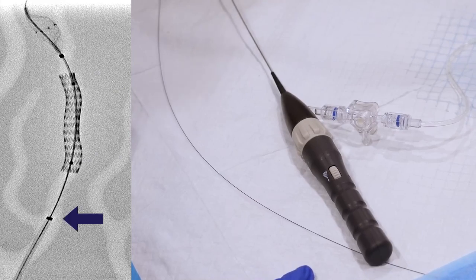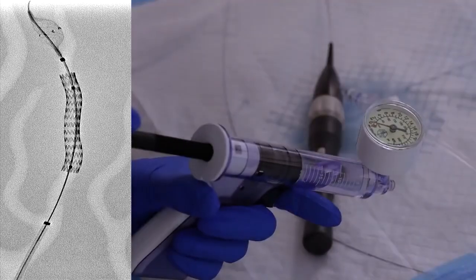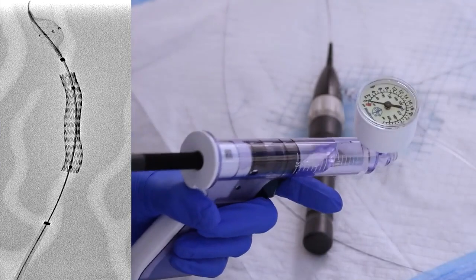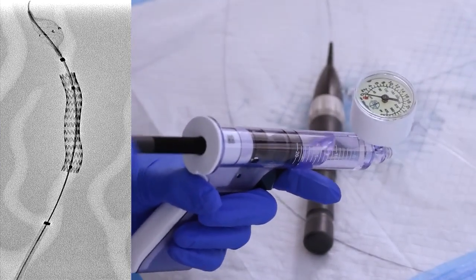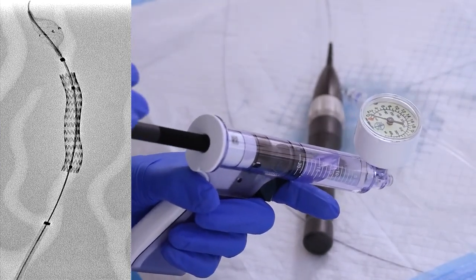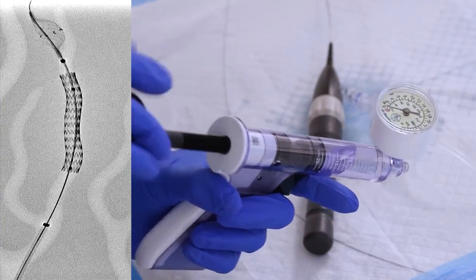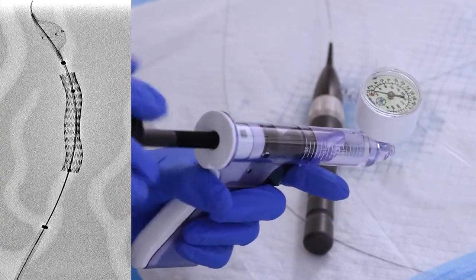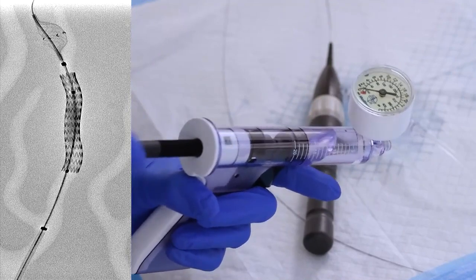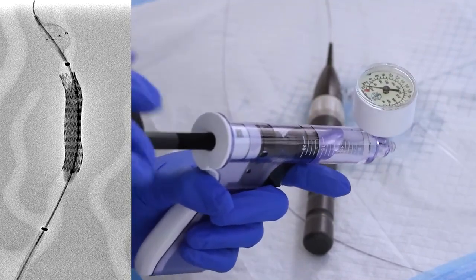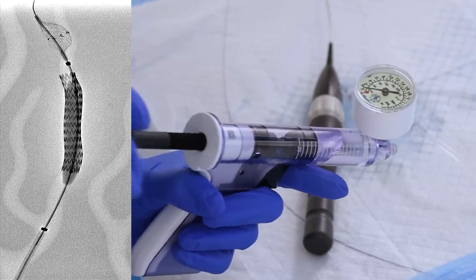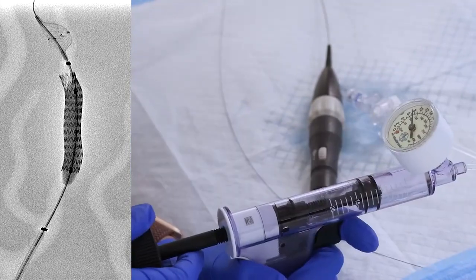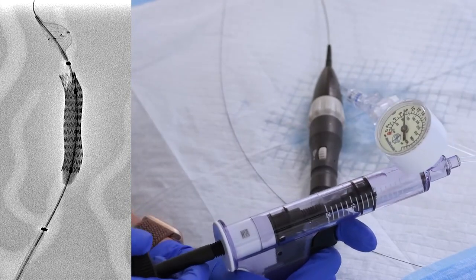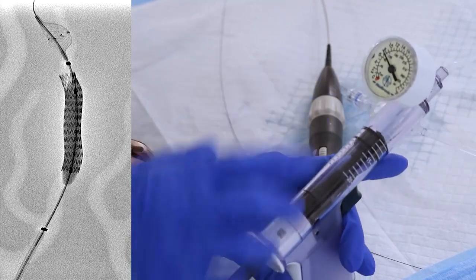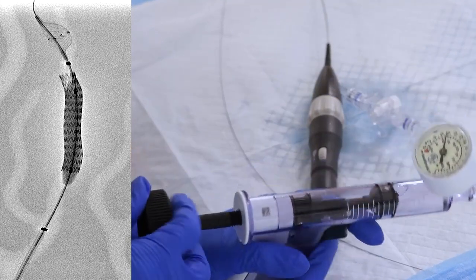Prior to post-dilation, ensure the pre-positioned balloon is within the stent. Using an inflation device, inflate the pre-positioned post-dilation balloon to the desired size, using the compliance chart in Table 14 as a guide. The inflated nominal diameter of the post-dilation balloon should be approximately the same as the diameter of the reference native vessel. Deflate the balloon after the desired size has been reached. At nominal pressure, 8 atmospheres, the balloon diameter will be 5 millimeters.